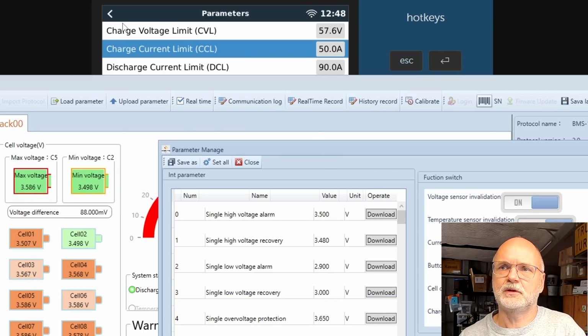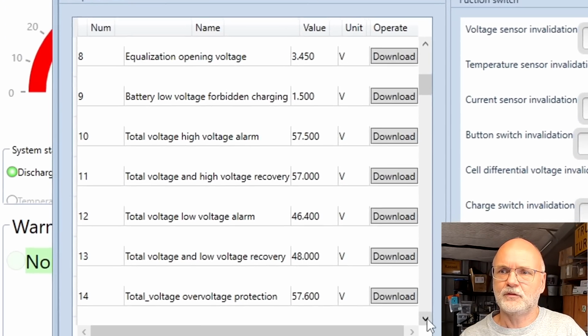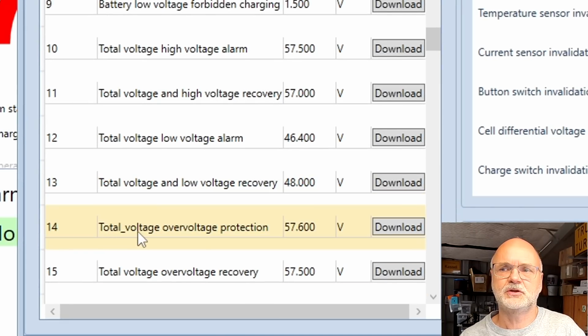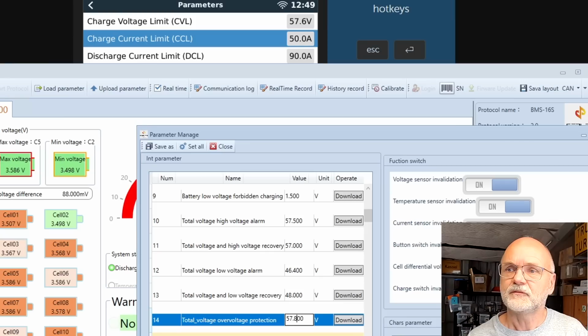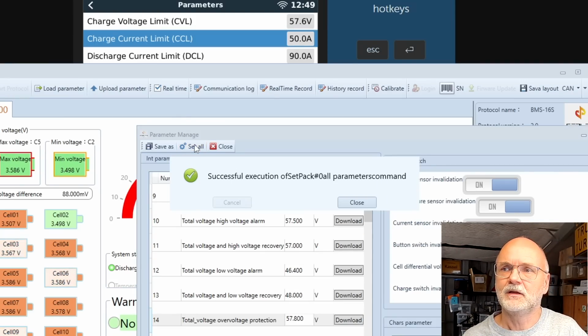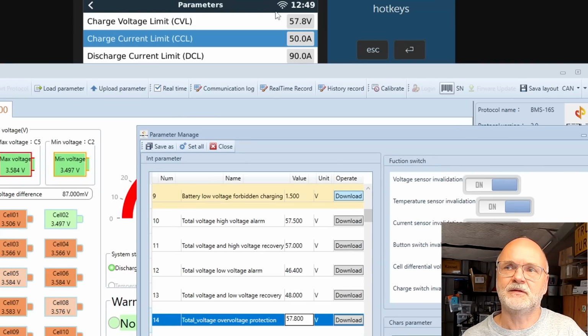What is actually responsible for the charge voltage limit, CVL? It is parameter number 14, the total voltage over voltage protection. This sits on 57.6. If I change this to 57.8, for example, and write the parameters back, you can see it changes up here in the Victron VRM.